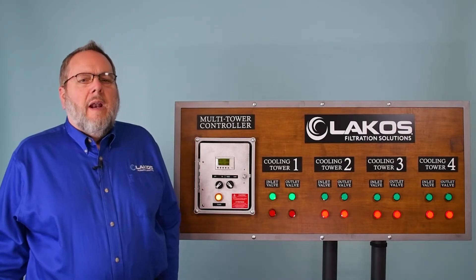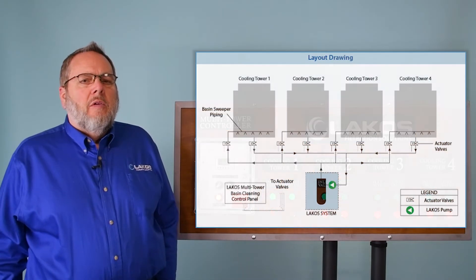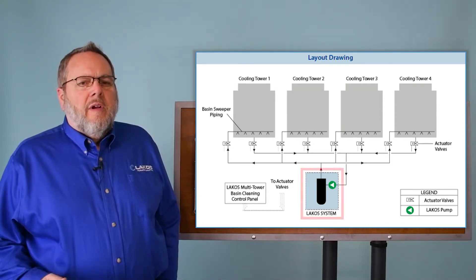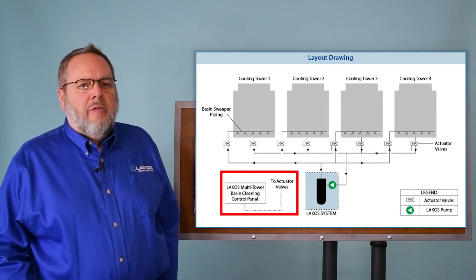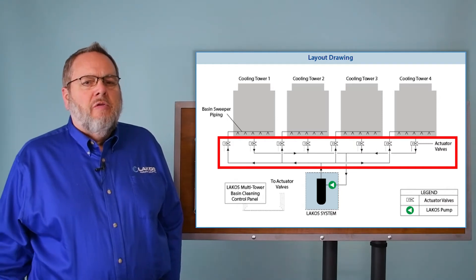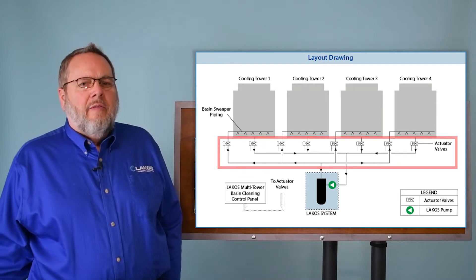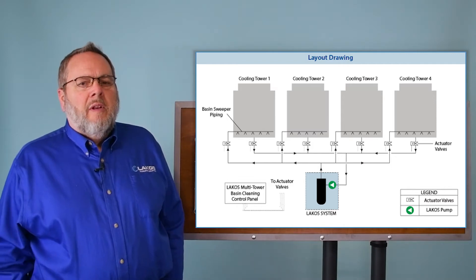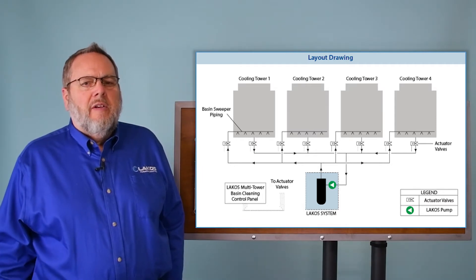Now we're going to look at how the multi-tower switching kit would work with a tower setup. What you see here is a piping and wiring diagram for four towers. You can see the LAKOS unit with the multi-tower switching kit next to it, and then headers and piping to each individual tower, with each inlet and outlet connection having its own set of valves. The LAKOS system itself is sized to sweep one tower at a time.